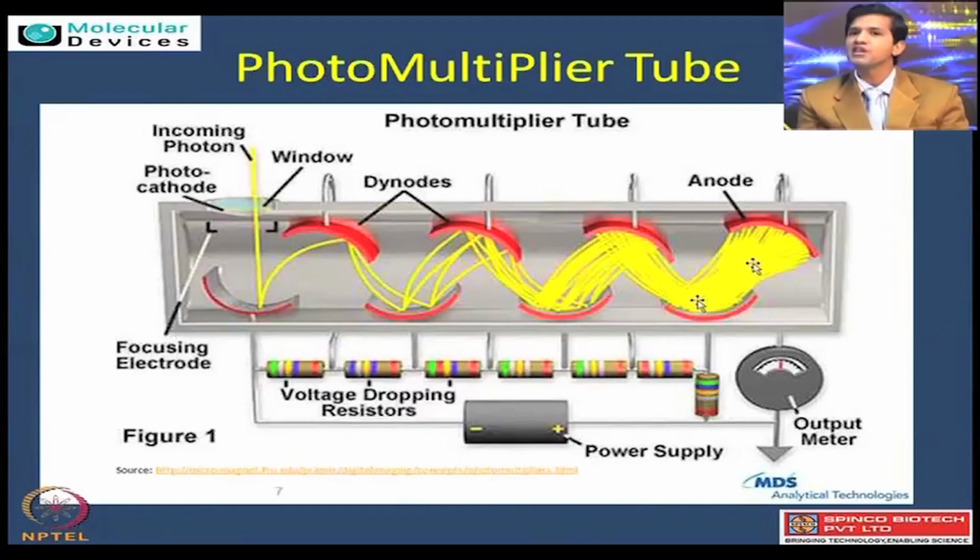The best way is to look at the photomultiplier tube setting. It ranges from something like 300 to 700, which helps one control how much photon multiplication can be done, so that the lowest signals can also be seen and the highest doesn't become saturated. So this is how the photomultiplier tube is very, very essential to control the different kinds of variability within the chip which happens due to the biology.